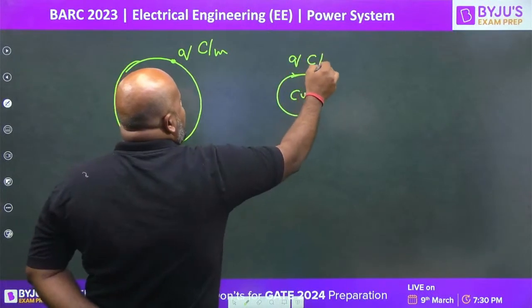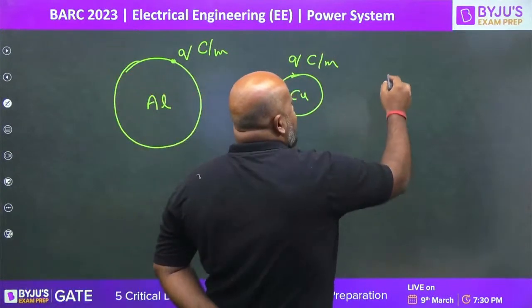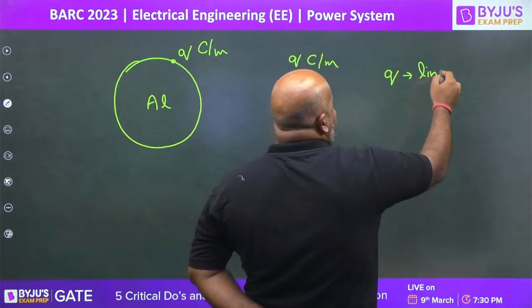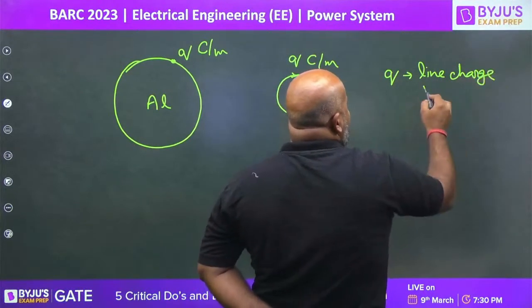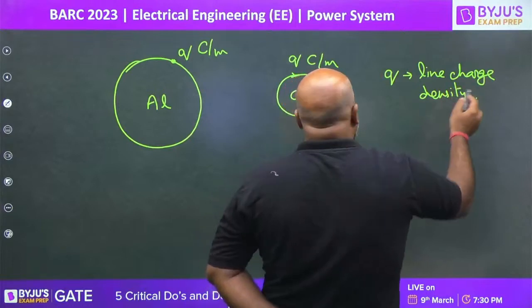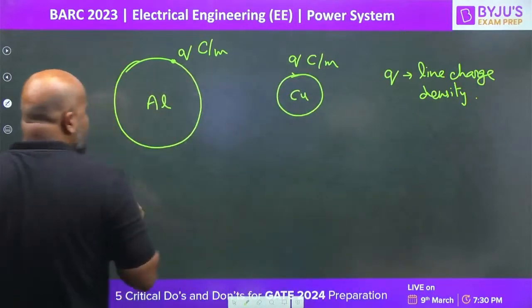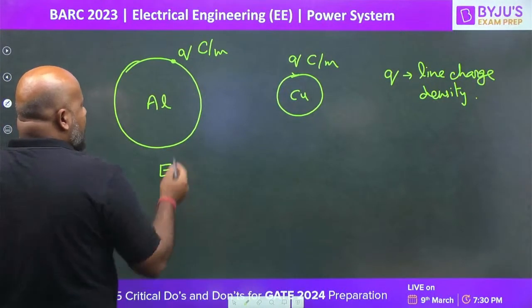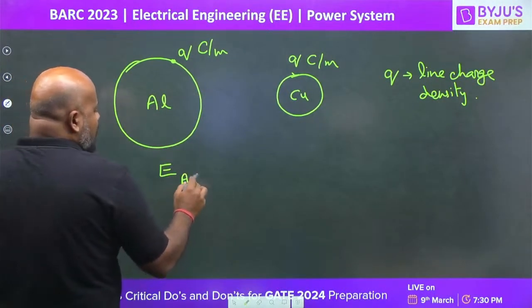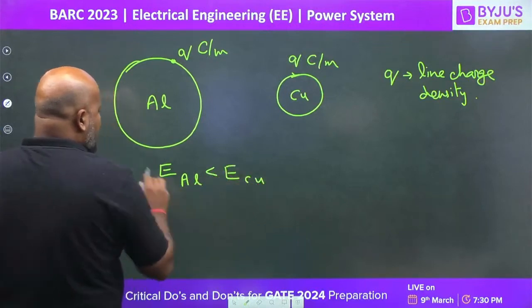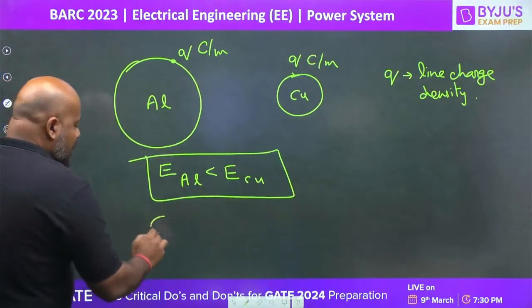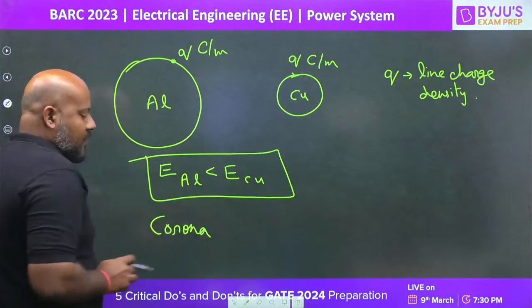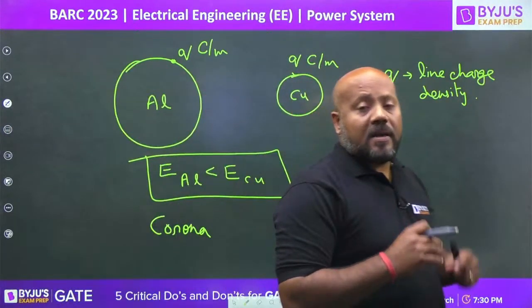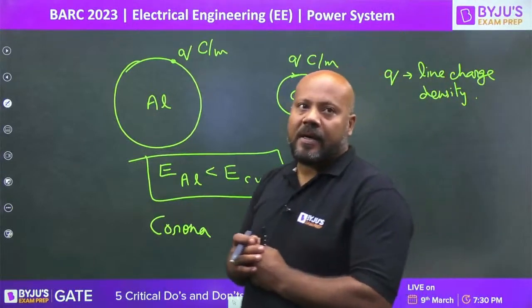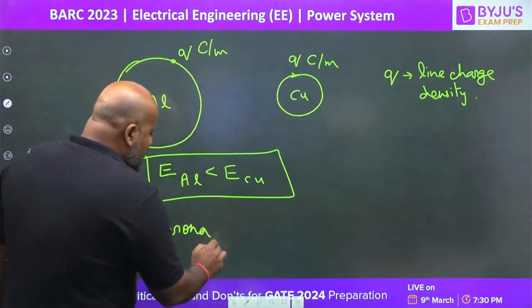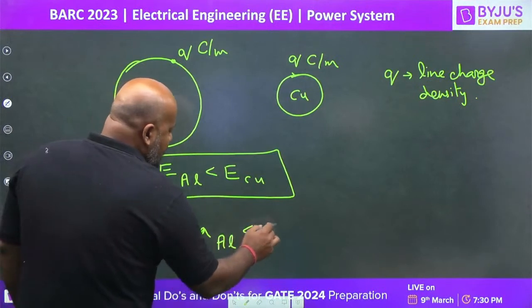If Q is the line charge density, then because of the higher radius for the aluminium conductor, the electric field stress at the surface of the aluminium conductor is going to be less than the electric field stress at the surface of the copper conductor. So for the same resistance and same length of conductor, the intensity of corona is going to be higher in case of copper conductor. So aluminium is going to be a better choice, yes or no?